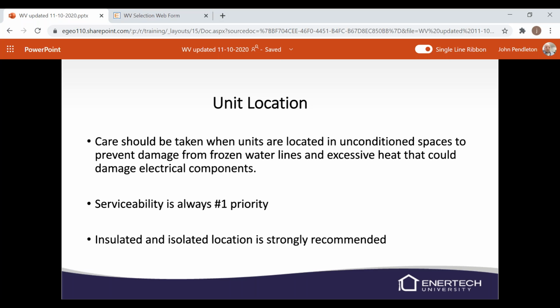Attics get kind of hot in the summer, so it could cause the drives to overheat, or there is an inverter fan on the unit that keeps the controls and the components cool. So if it gets too hot in there, it will lock the unit out. Make sure that we're always giving a way to be able to service the unit. Serviceability, at some point, the unit's going to have to be worked on. That's just the way the equipment is. And so serviceability is always priority number 1. I would say, 2 foot around the entire unit, but that's a perfect world. If you can't do that, we would recommend at least the front and 1 side. The back side is where the water lines come out, and you'll see it here in a few minutes.